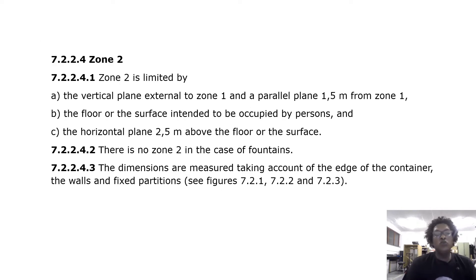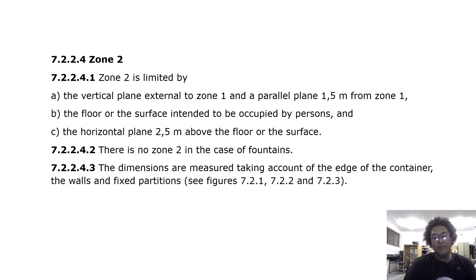Zone 2 is limited by the vertical plane external to zone 1 and a parallel plane 1.5 meters from zone 1, the floor or surface intended to be occupied by persons, and the horizontal plane 2.5 meters above the floor or surface. There is no zone 2 in the case of fountains. The dimensions are measured taking account of the edge of the container, the walls and fixed partitions — see figures 7.2.1 to 7.2.3.